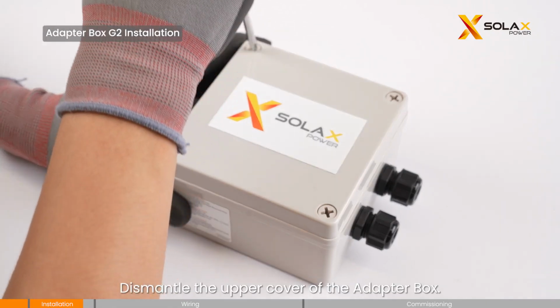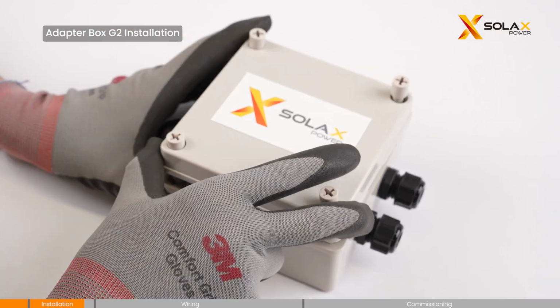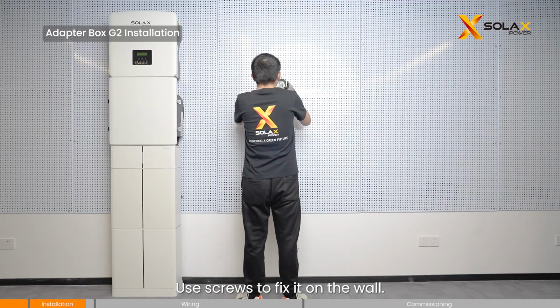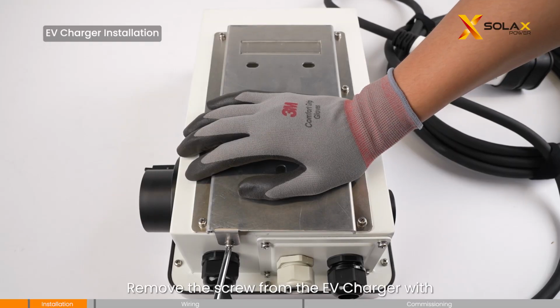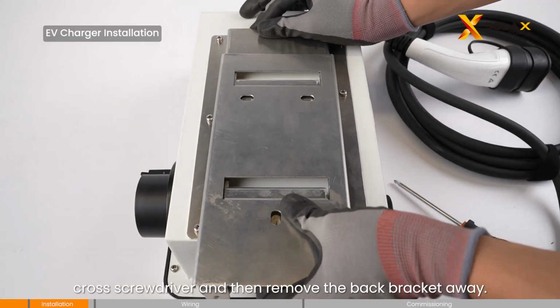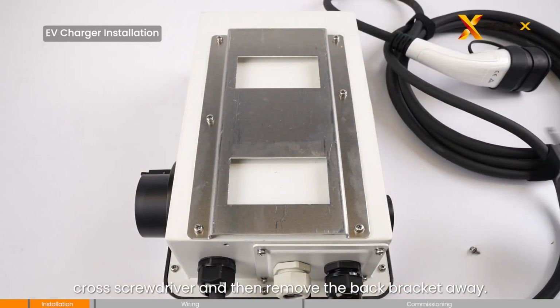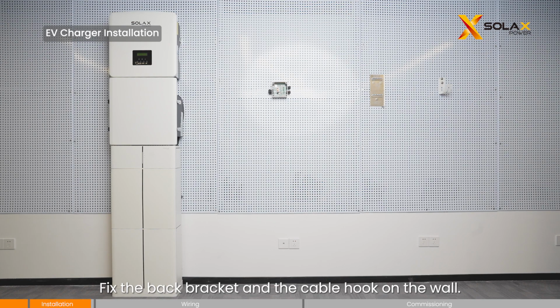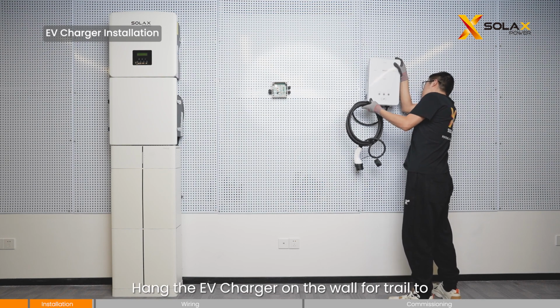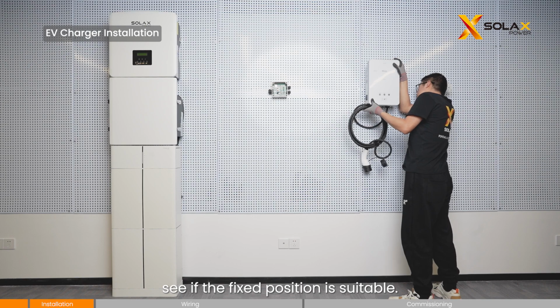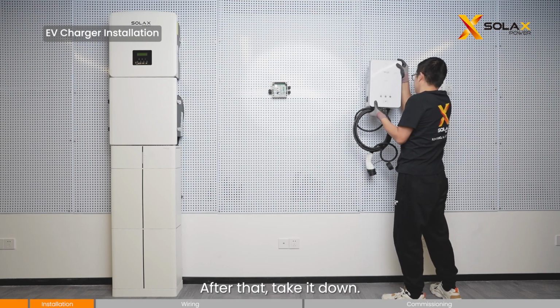Dismantle the upper cover of the adapter box. Use screws to fix it on the wall. Remove the screw from the EV charger with cross screwdriver and then remove the back bracket away. Fix the back bracket and the cable hook on the wall. Hang the EV charger on the wall for trial to see if the fixed position is suitable. After that, take it down.